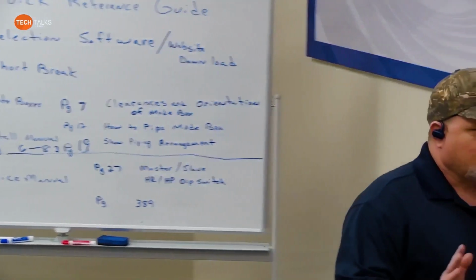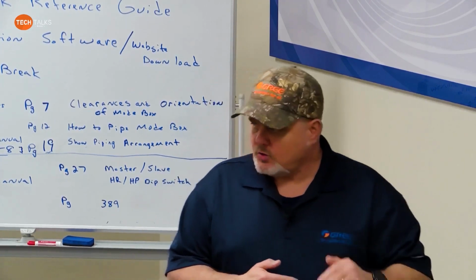So when you're addressing things, not only do you want to go through and make sure you know which indoor units are at what address, where it's at, so when you set up central control, you can name it. Like, this is front office, this is back office, this is the conference room, whatever labeling you want to put on it, so that you know each one of those units when you set up central control, you know what part of the building it's in, all the way through.